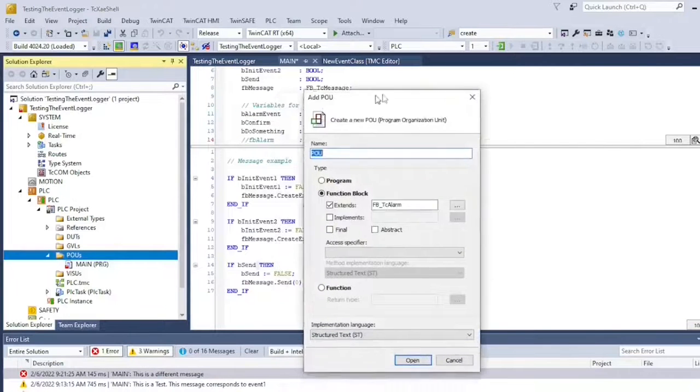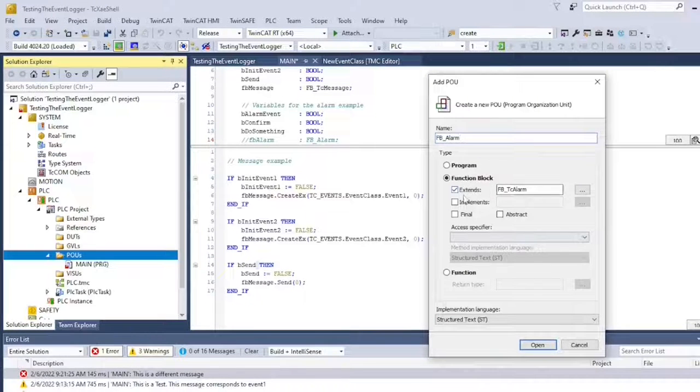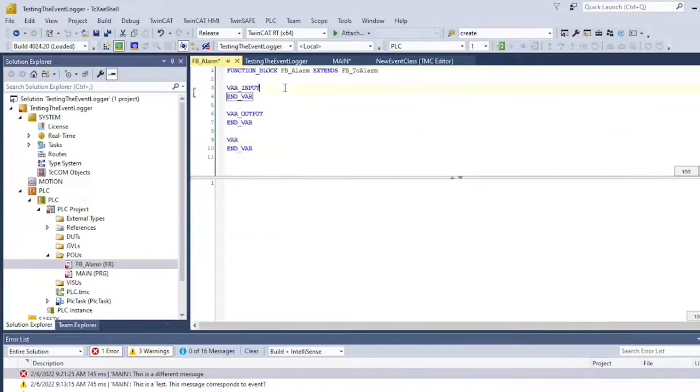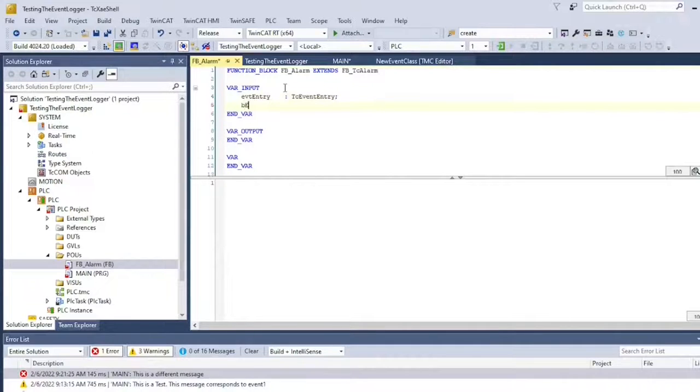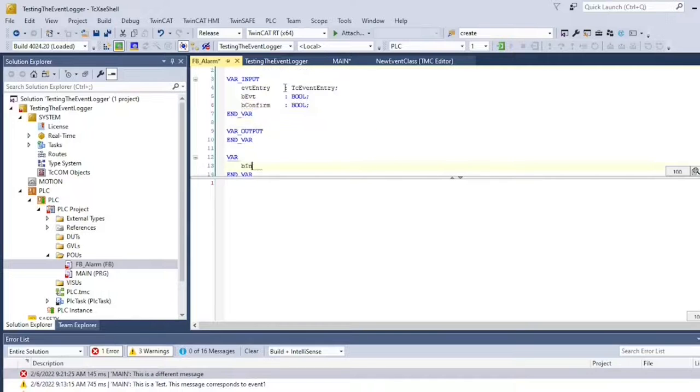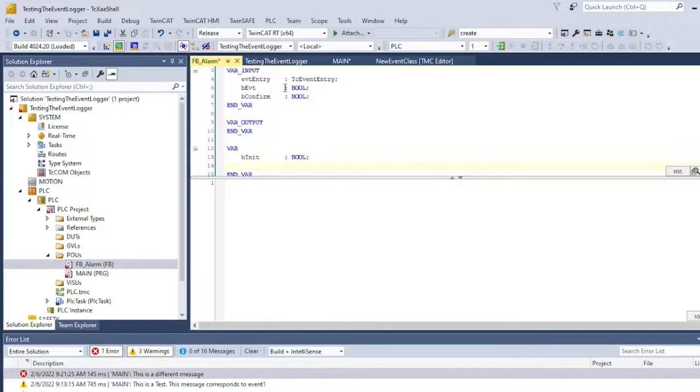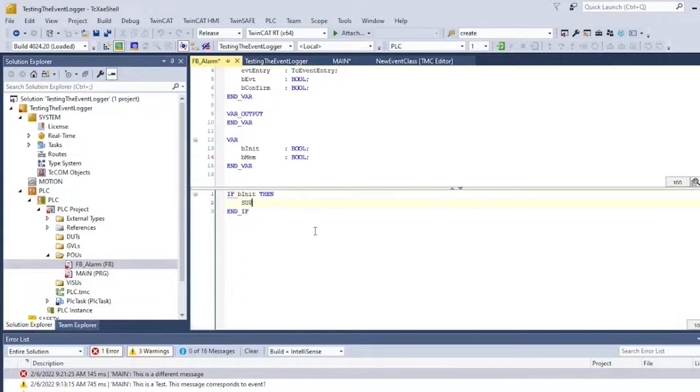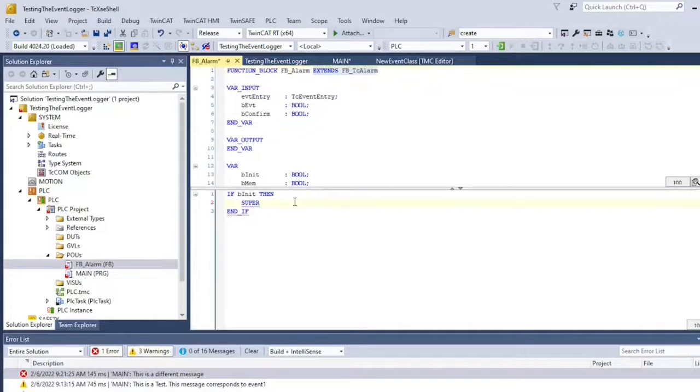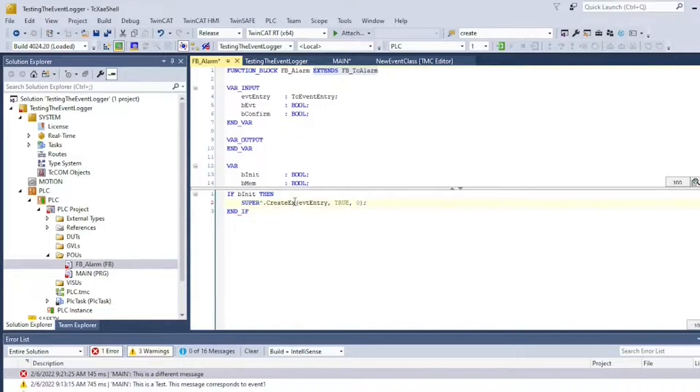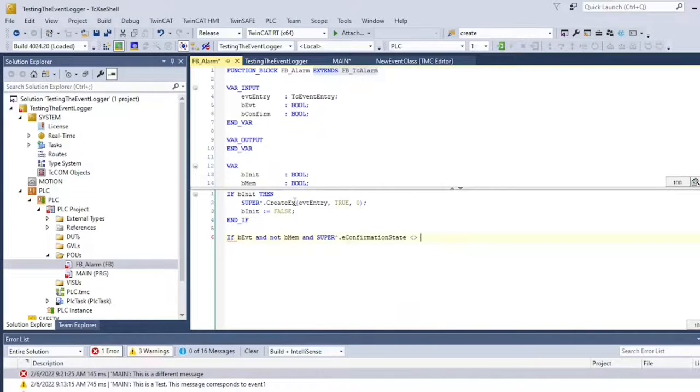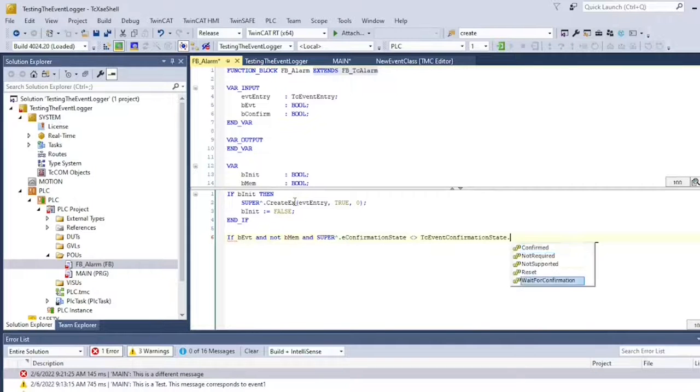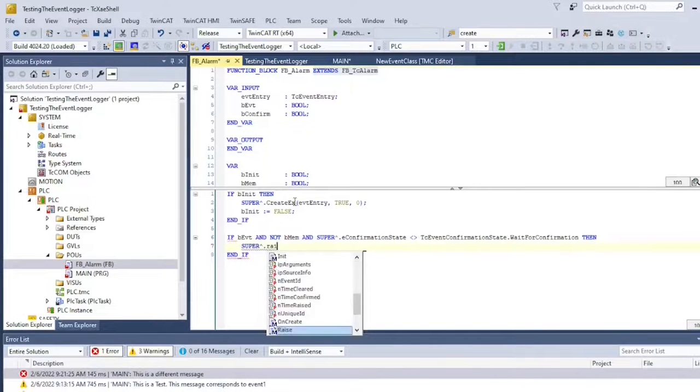So add a new POU and make sure that it inherits or extends from FB TC alarm. Our inputs are an event entry, an event trigger, a confirmation bit. We also need a couple of auxiliary boolean variables. So when we call this function block, an alarm is created through the createEx method from FB TC alarm and bitInit is reset to false.